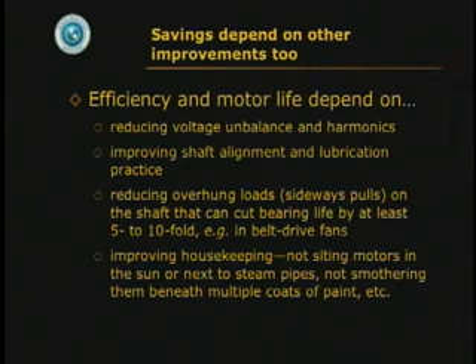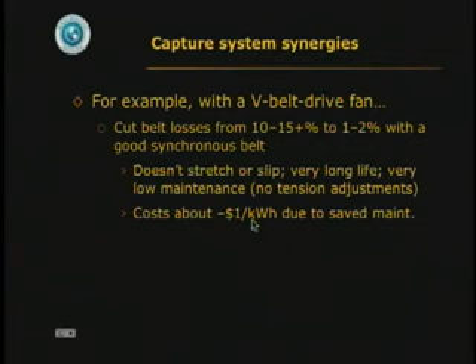Of course, efficiency and motor life depend on a lot of other things too, like not putting motors in hot places or smothering them in multiple coats of paint, not pulling sideways on the shaft with a V-belt that wears out the bearings, having proper shaft alignment and lubrication practice. It turns out if you replace that fan V-belt, which is a very common thing to see, with a good synchronous belt with teeth engaging cogs, you enormously reduce the losses and the maintenance, so much that just the same maintenance pays for each saved kilowatt hour with $1 left over in your pocket.